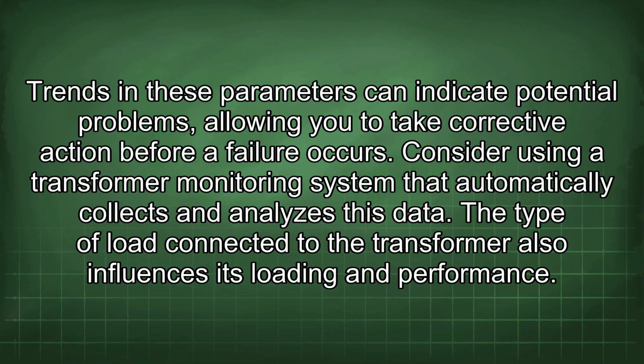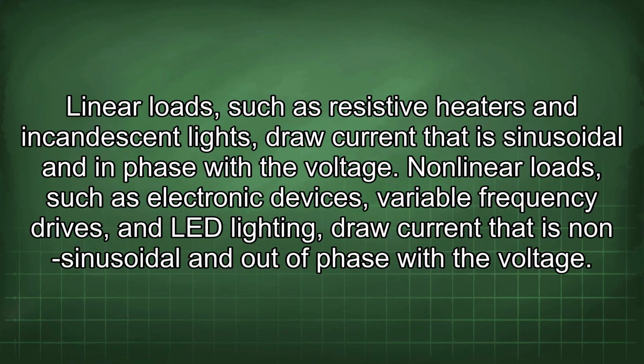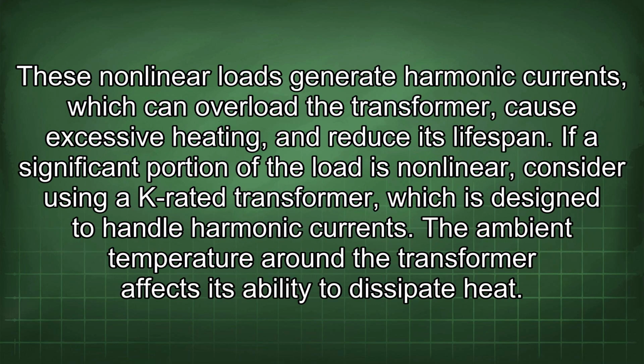The type of load connected to the transformer also influences its loading and performance. Linear loads, such as resistive heaters and incandescent lights, draw current that is sinusoidal and in phase with the voltage. Nonlinear loads, such as electronic devices, variable frequency drives, and LED lighting, draw current that is non-sinusoidal and out of phase with the voltage. These nonlinear loads generate harmonic currents, which can overload the transformer, cause excessive heating, and reduce its lifespan. If a significant portion of the load is nonlinear, consider using a K-rated transformer, which is designed to handle harmonic currents.